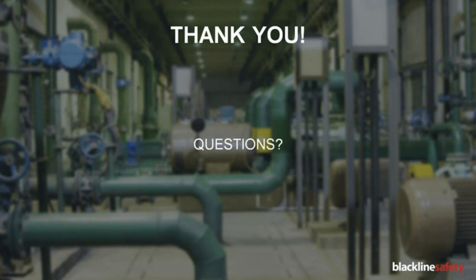Yes, so they should be bump tested. In Canada, that's actually a legislated requirement if you've got an LEL sensor. In the States, I don't think it's legislated, but it's definitely a best practice. For calibration, we recommend every 6 months. You can invoke both of these directly from the menu on the device—just scroll through with the buttons and say you want to calibrate now. We ship a cal cap in the box with the device, so then you just need a gas tank and a hose—actually, we supply the hose too, so you just need a gas tank and a regulator. You can hook it up with what's in the box and calibrate or bump directly from there.